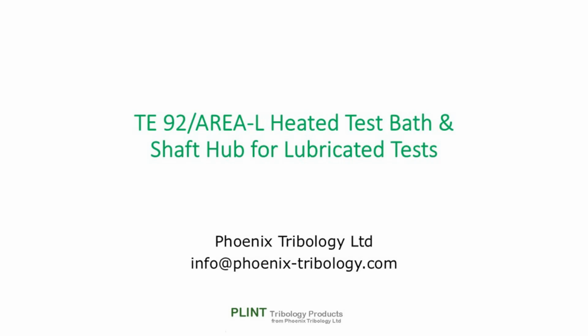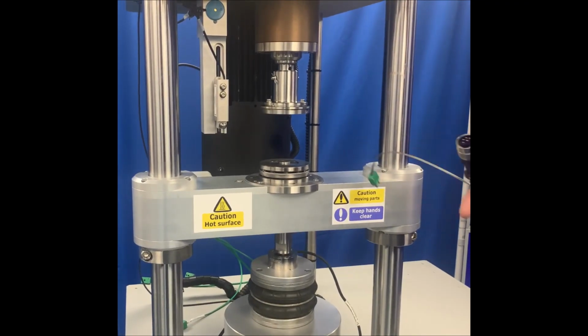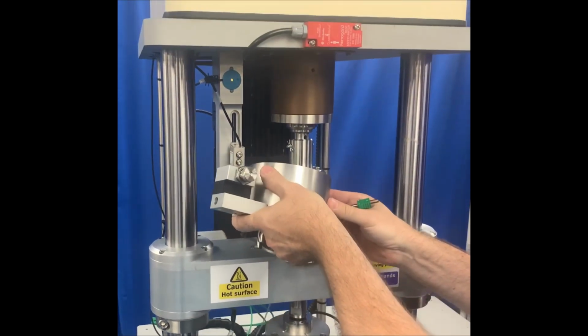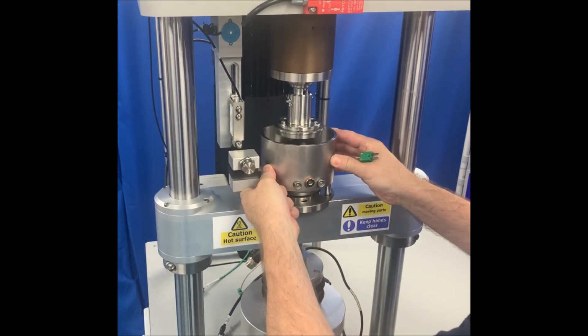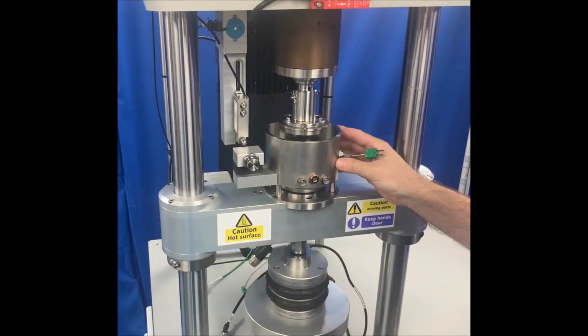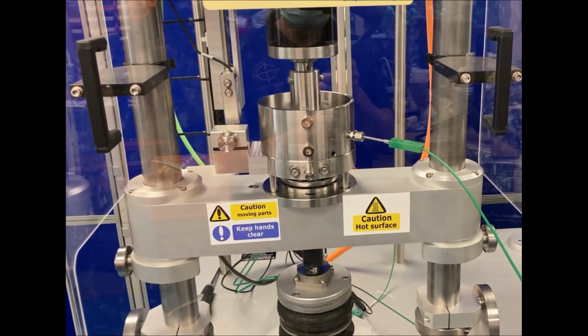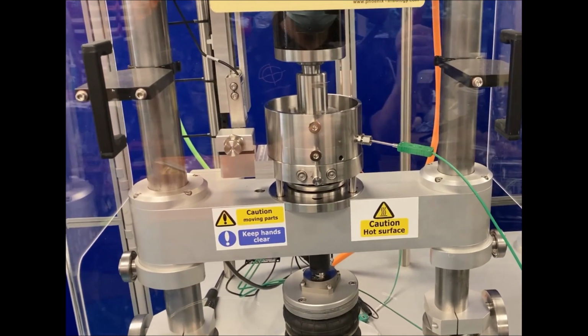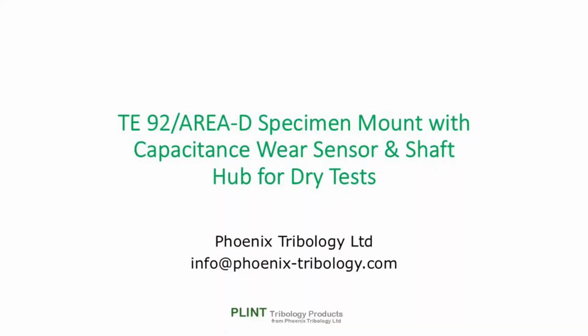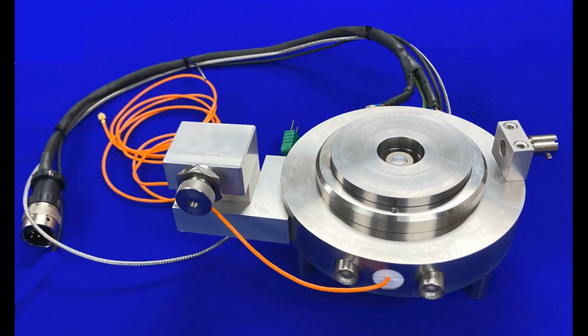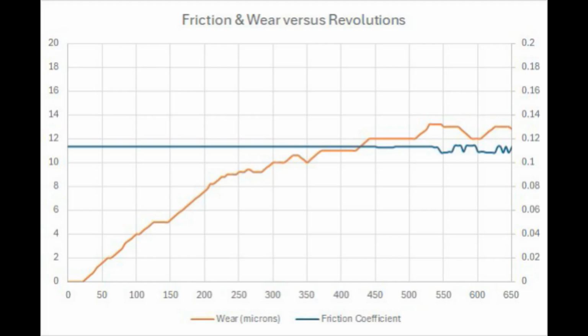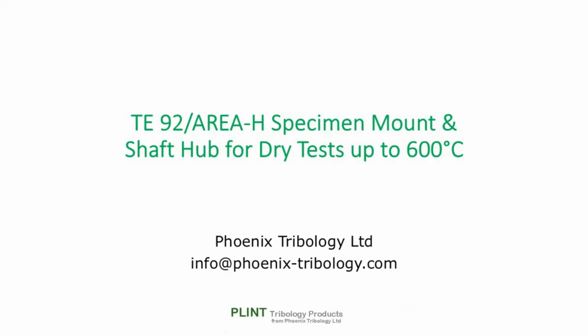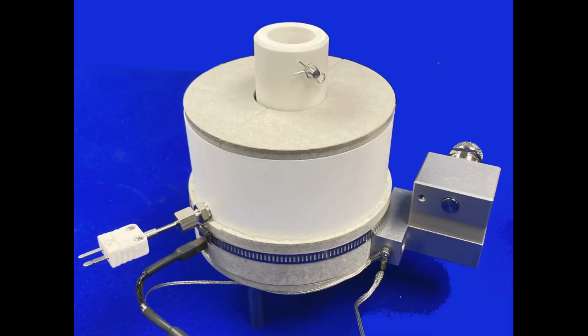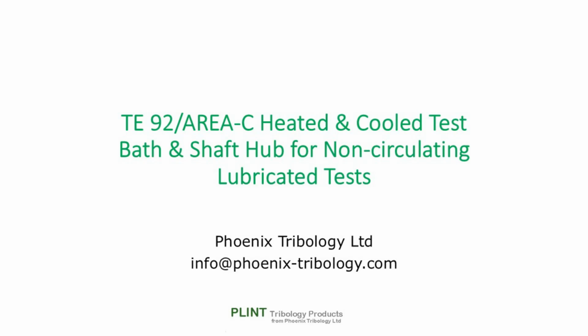For sliding tests with area contact specimens, we have 4 standard test adapters, starting with a heated test bath for lubricated tests. For dry tests in 3-pin-on-disc and thrust washer configurations, we have an adapter with a centrally located capacitance probe for non-contact online wear measurement. For dry tests at up to 600 degrees C, a heated test enclosure is available. Finally, we have a bath which combines both heating and cooling.